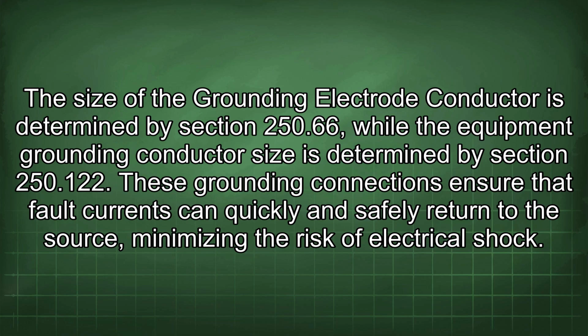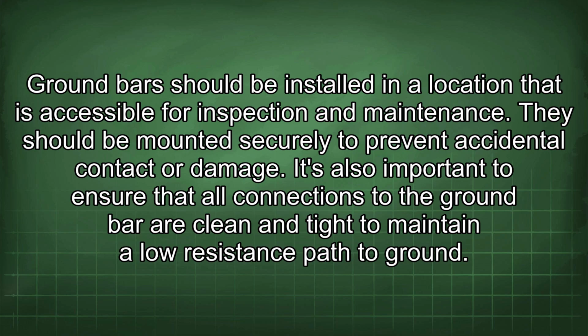These grounding connections ensure that fault currents can quickly and safely return to the source, minimizing the risk of electrical shock. Ground bars should be installed in a location that is accessible for inspection and maintenance. They should be mounted securely to prevent accidental contact or damage.